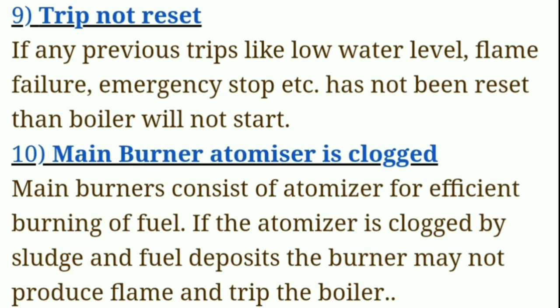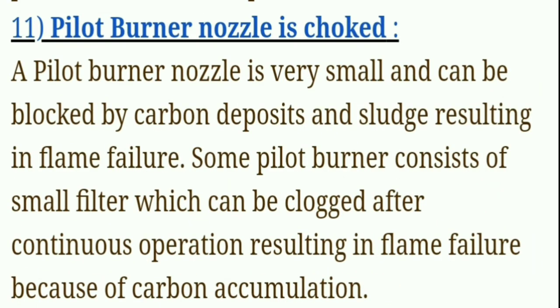Eleventh, the pilot burner nozzle is blocked. A pilot burner nozzle is very small and can be blocked by carbon deposits and sludge, resulting in flame failure. Some pilot burners also consist of a small filter which can be clogged after continuous operation, resulting in flame failure due to carbon accumulation.